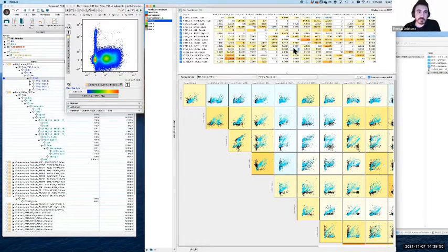If I turn this up much higher, it's going to push this population that's going up and down. It's going to push it to the left. In terms of the value being applied, it's trying to remove it from the non-target detector, just like that. So that's clearly an example where the compensation has gone too far. It's been too excessively extracted from the non-target detector. Maybe I'll make it a tiny bit lower just to make it a bit more interpretable. So that's the classic curve that we're trying to look for. There's a couple of situations we'll come to where it's not always clear which is the offending fluorophore. It may not always be easy to interpret.